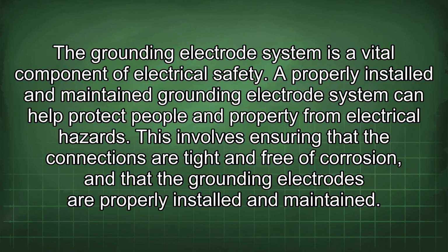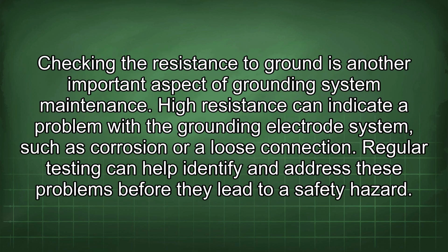This involves ensuring that the connections are tight and free of corrosion, and that the grounding electrodes are properly installed and maintained. Checking the resistance to ground is another important aspect of grounding system maintenance. High resistance can indicate a problem with the grounding electrode system, such as corrosion or a loose connection. Regular testing can help identify and address these problems before they lead to a safety hazard.